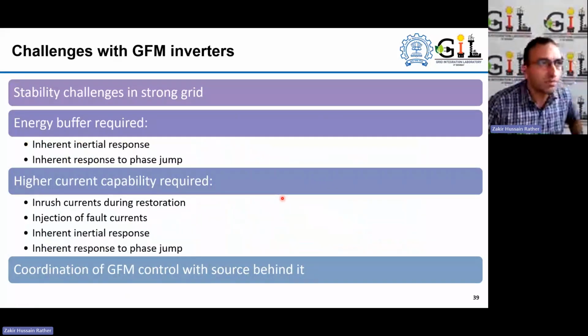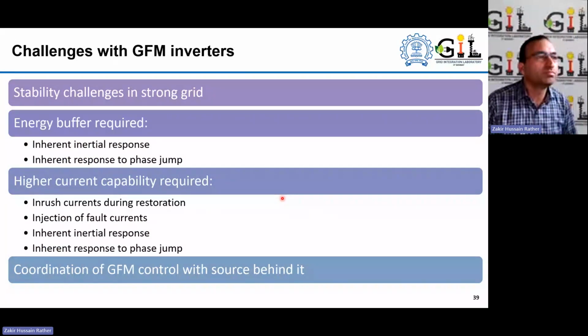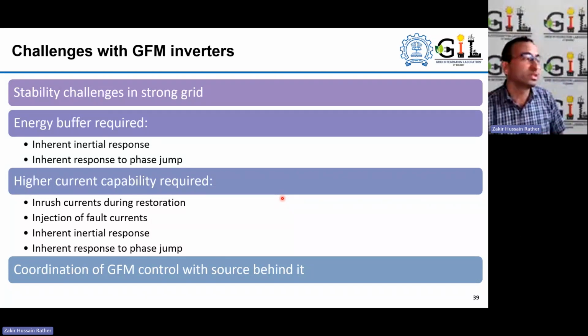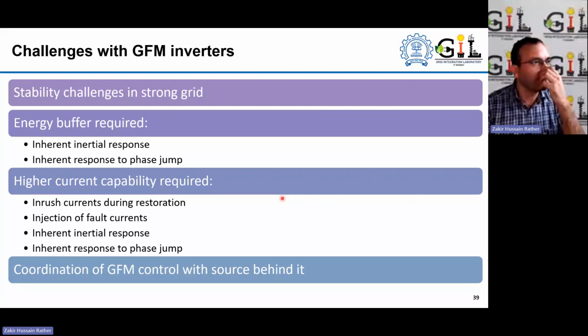So these are some of the capabilities of this grid forming technology, but not everything is by default good with grid forming technology. There are challenges and limitations. There are stability issues with grid forming technology in a strong grid, and if not carefully addressed or taken into account, it can lead to stability issues in the strong grid. So we have a reverse issue here. We had an issue in the weak grid with grid following, but we have challenges in the strong grid with the grid forming technology.